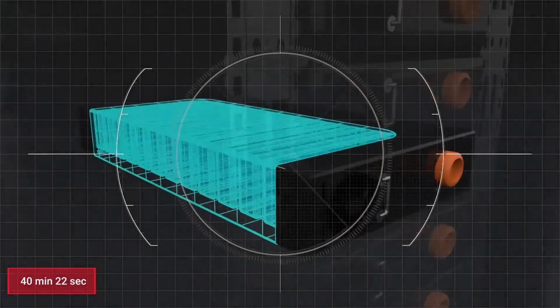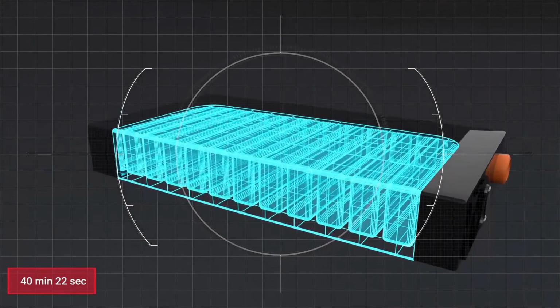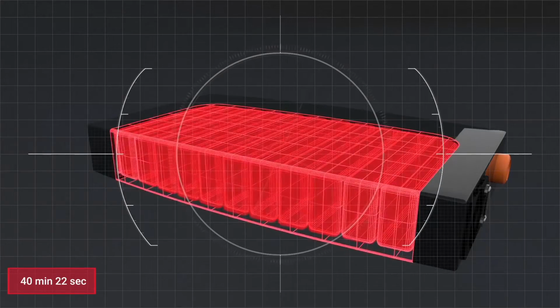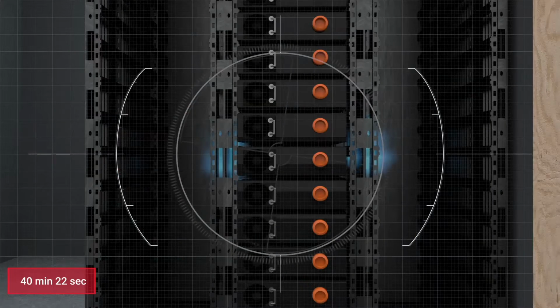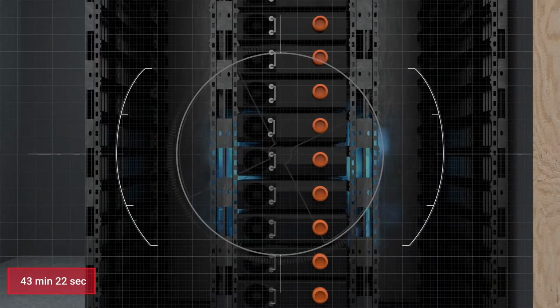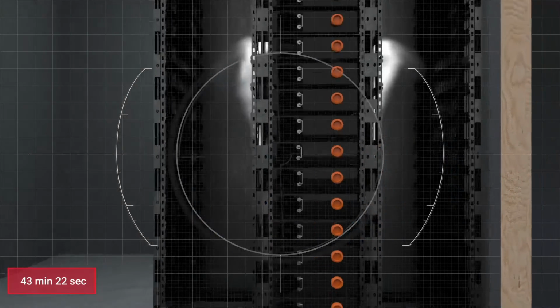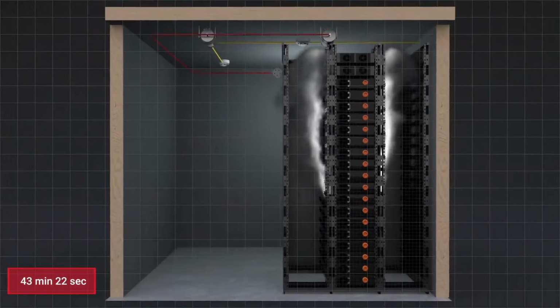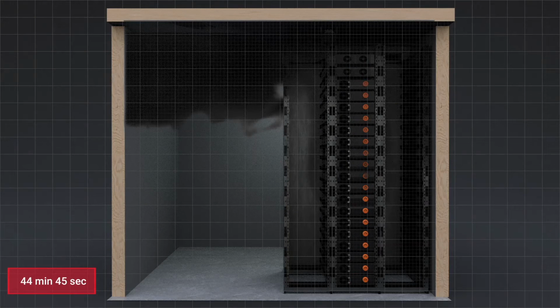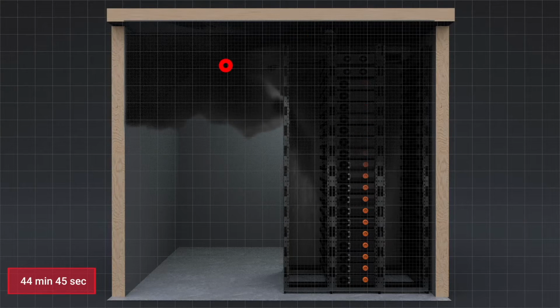At 40 minutes and 22 seconds after heating began, the first indication of thermal runaway was detected as the battery units emitted hydrogen. At 43 minutes and 22 seconds, light smoke was detected and the first smoke alarm was activated. At 44 minutes 45 seconds, heavy smoke was building within the enclosure and the second smoke alarm was activated.